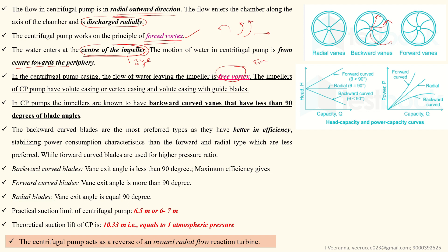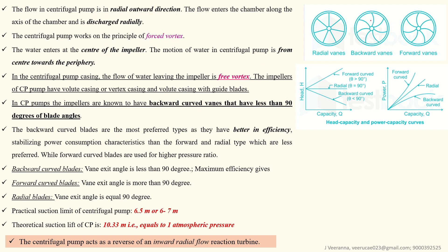The blade angle is also an important topic. Backward curved vanes have an angle less than 90 degrees and have higher efficiency, so they are most commonly used. Forward curved vanes have angles greater than 90 degrees. Radial vanes are at exactly 90 degrees. The backward blades curve in one direction while forward blades curve in the opposite direction.